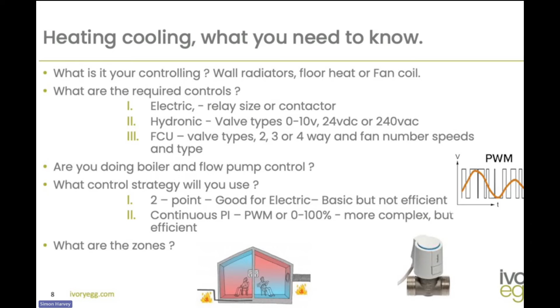And then we've also got to consider our zones and how we're controlling the zones, where our thermostats are and where our input temperatures are for these zones. With heating and cooling, there are 4 major parts to any heating and cooling system. There's the thermostat controller. You've got to be careful with definitions here. What I mean by that is this is the human interface, or the user interface, that decides what they're asking from the heating and cooling. Okay, so I want the floor temperature to be 23 degrees and I want it in comfort mode, and so forth. That is the input from the user.